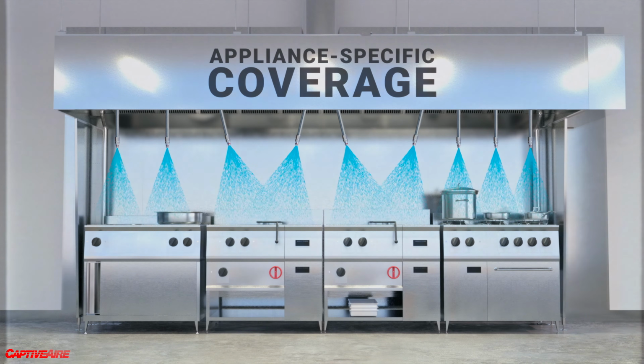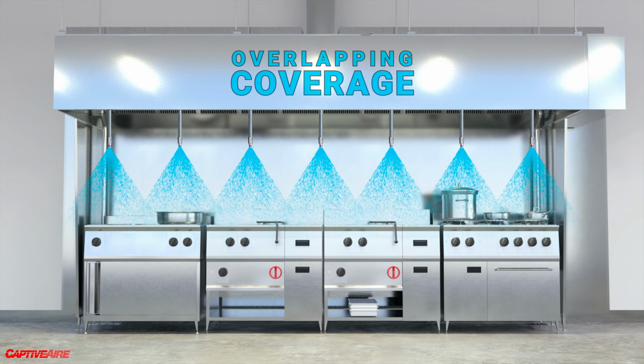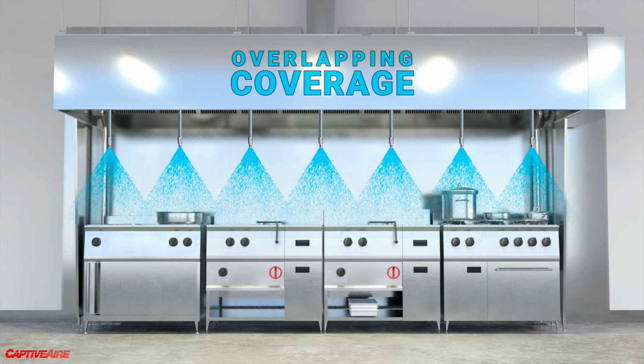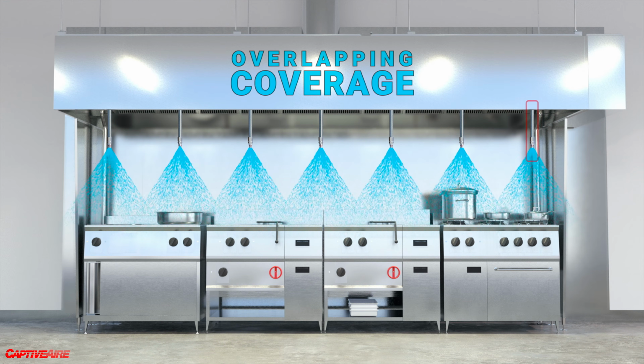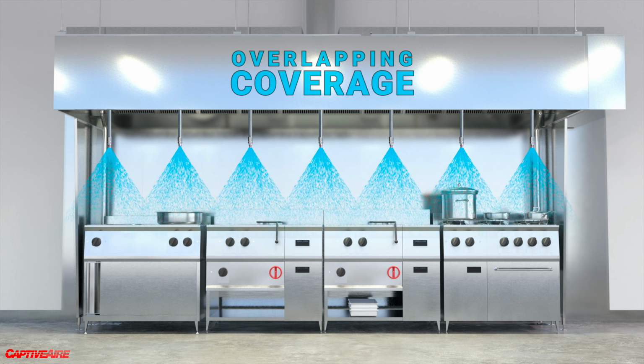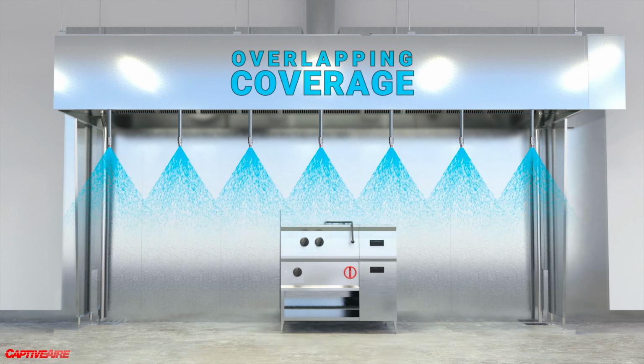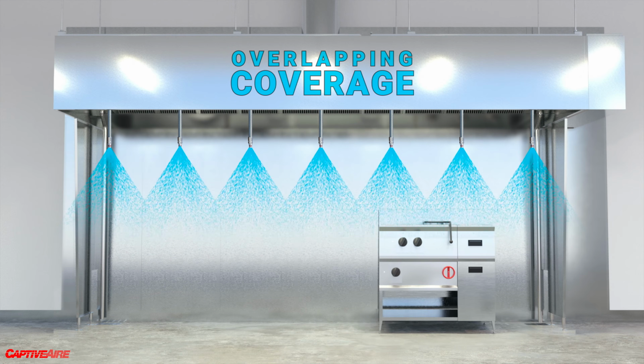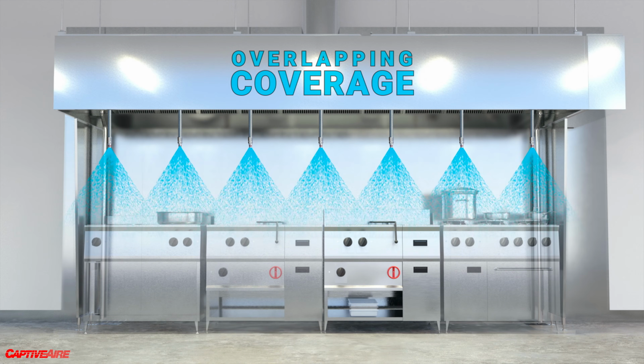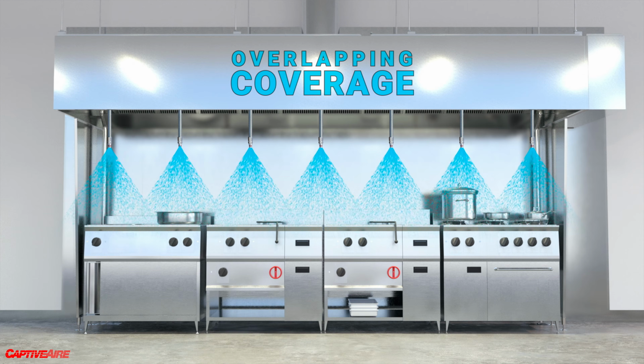But CaptiveAire prefers to use what's called overlapping coverage whenever possible. Overlapping coverage is equally spaced nozzles along the length of the hood to cover a various amount of appliances that can be placed wherever within that zone. Overlapping means the spray pattern of the nozzles is literally overlapping, giving us full coverage across the hood.